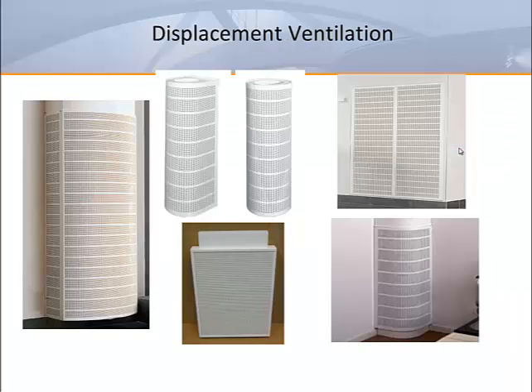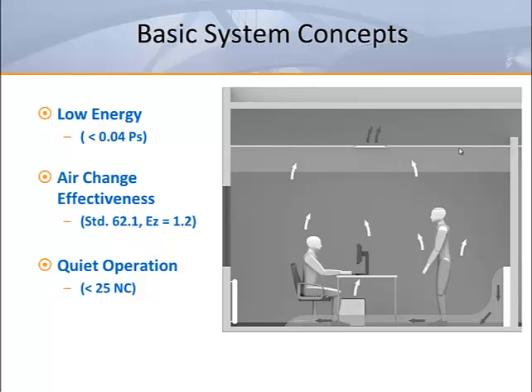There is a large variety of displacement ventilation outlets to choose from in meeting the architectural and performance requirements. A disadvantage is that they are mounted at the floor and take up a great deal of floor and/or wall space. The advantages do outweigh the negatives. Displacement ventilation outlets operate at very low pressure losses, typically less than 0.04 inches of static pressure at maximum airflow. This is lower than comparable mixed air outlets.